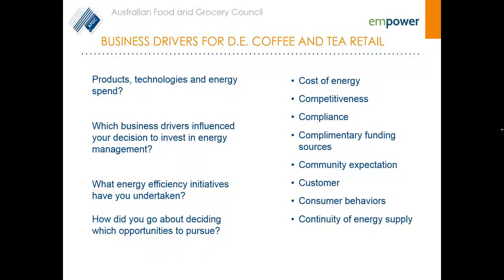With regards to air compressors, we had 2 air compressors which were over capacity for what we actually need here, and neither of them were VSDs. So we replaced one with a smaller VSD air compressor, and with that project we also went to a leasing arrangement. Rather than capitalise the new one, we're leasing it, and that's working out a lot better for us from a cost perspective. We're getting a good energy saving, and we're also showing the cost benefit a lot sooner with just leasing it.